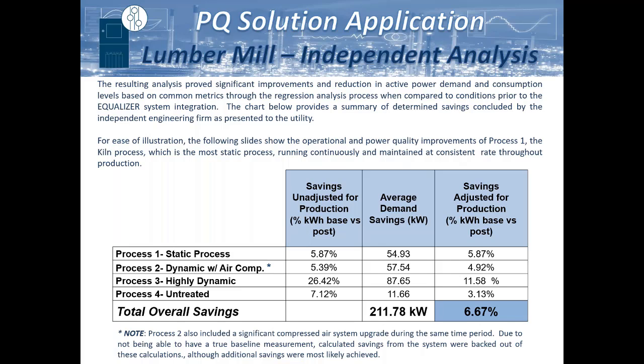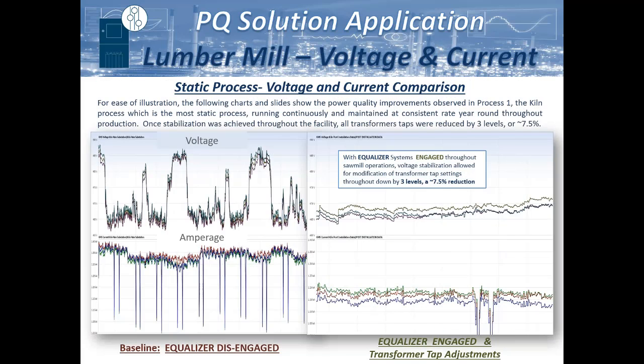So the more dynamic the process is, oftentimes the better the improvements and the results. We even had benefits in areas that weren't treated, because when the sawmill was in production, they were averaging about 470 volts on a 480 volt network. But when the sawmill was not in production, they were running about 515. So here, because it's the easiest way to illustrate this, this is actually the kiln. So it's a very steady state process, but you can tell whenever the sawmill was engaged versus disengaged, has a significant impact on the voltage. And you can even see how it impacts the current draw on this network as well.